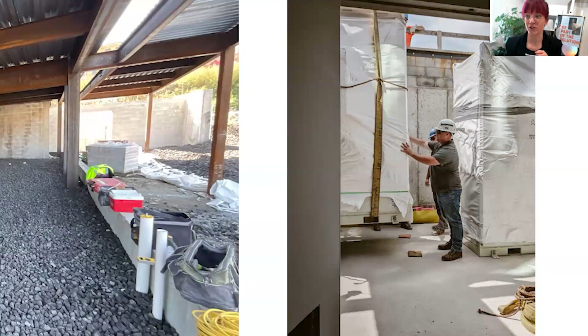And so we changed this right at the perfect time where we could modify just slightly the dimension of the room. It was almost where it needed to be, but the big difference is that it needed to be taller. So these batteries are housed in fire-safe cabinets. We have 2 cabinets on the job, and they have a deflagration panel on the top.